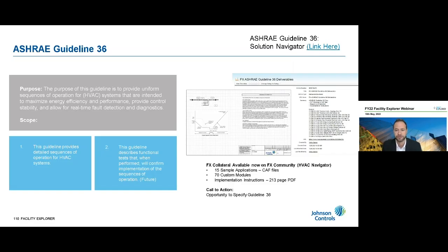Starting with ASHRAE Guideline 36, this is a guideline issued back in 2018, and its purpose is to standardize or provide a uniform sequence of operation for HVAC control systems. The intent is to maximize energy efficiency and performance, provide control stability, and allow for fault detection and diagnostics.